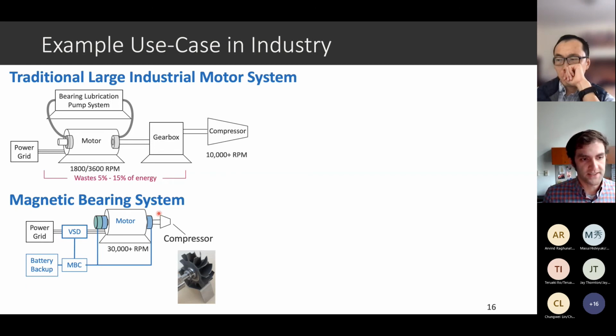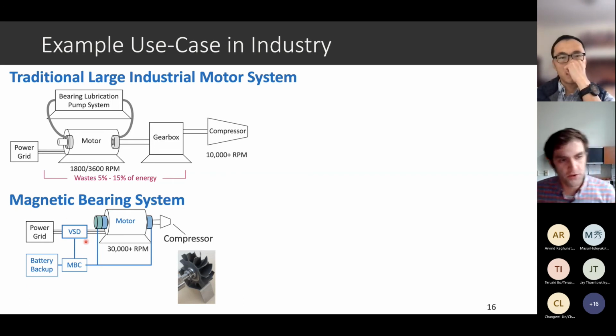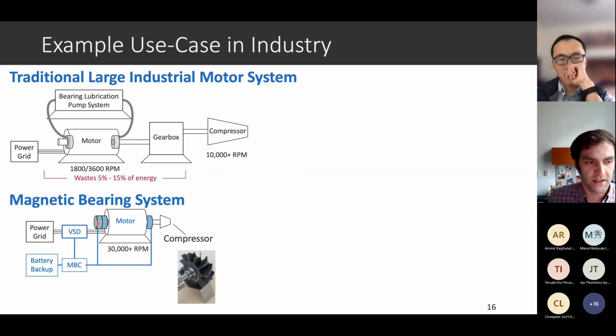So the magnetic bearing system kind of leapfrogs this issue. You can put your motor drive on here because your magnetic bearings are levitating your shaft, so there's no place for those bearing currents to flow. In this case, we've got a motor, and we're going to right away make it a high-speed motor because our compressors like to be high-speed.